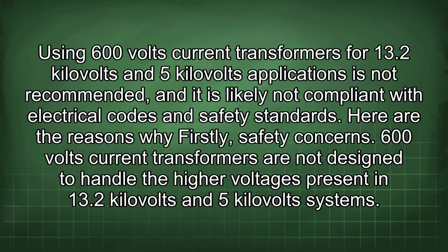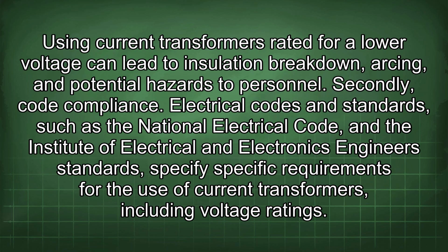Using 600 volts current transformers for 13.2 kV and 5 kV applications is not recommended, and it is likely not compliant with electrical codes and safety standards. Here are the reasons why. Firstly, safety concerns. 600 volts current transformers are not designed to handle the higher voltages present in 13.2 kV and 5 kV systems.